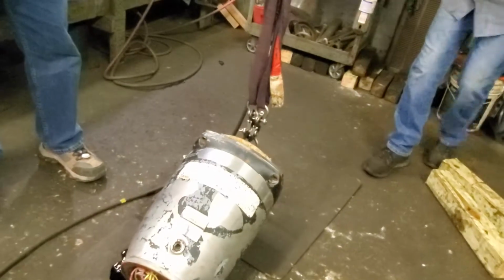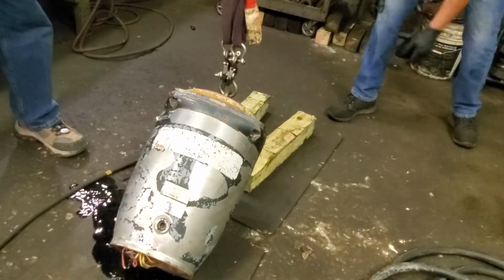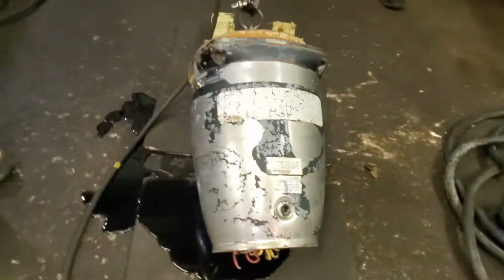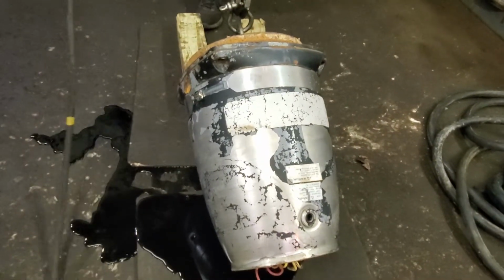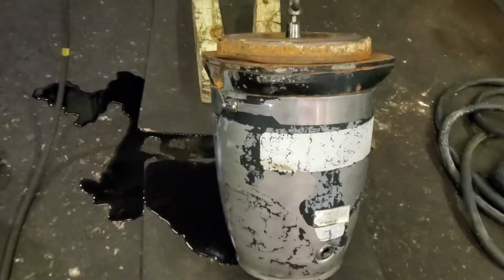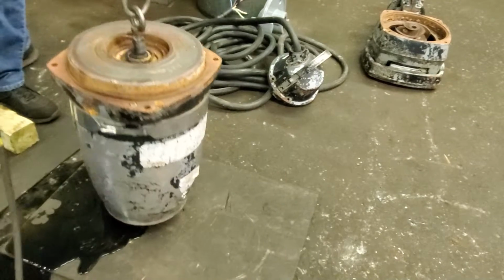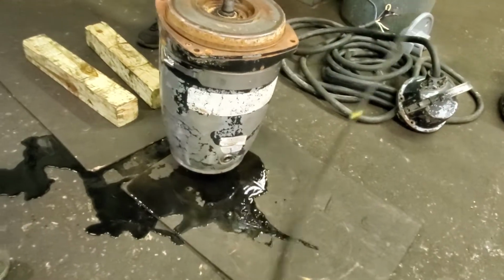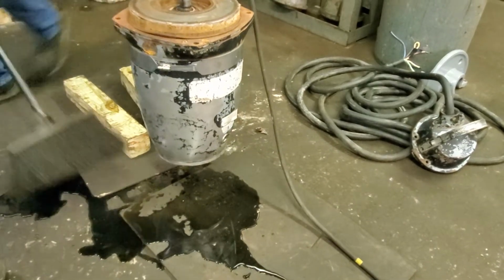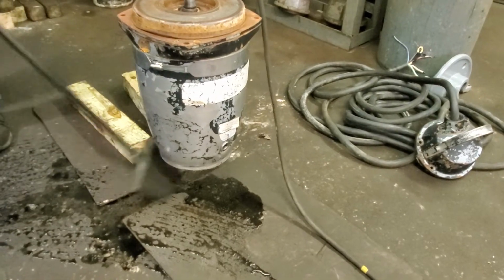There's a little water in there. Oh man. See the little water in there, but it looks like sewage water. That's not coolant. So I really think the seal failed. That means if they put the coolant in there, the seal failed, maybe the coolant leaked out and the sewage water came in. So possibly the seal failed, the coolant leaked out, and it was replaced by sewage water.